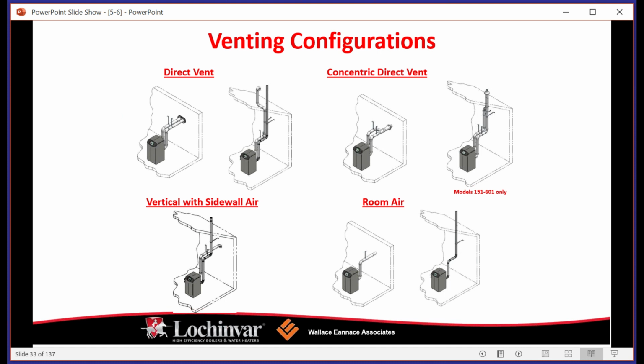Concentric vent kits. If you haven't seen them, a concentric vent kit is essentially a kit you use where you need a single penetration to gather your combustion air and expel your flue gases, using a conical device that pulls the combustion air through one side and pushes the flue gases out through the other. Again, you can push that out for sidewall venting. That can go out through the roof as well. We can switch it up.